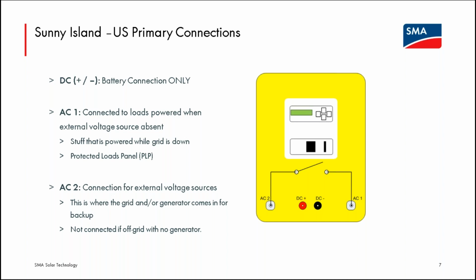If someone is using the system with a generator, the generator would also connect to the AC2 terminals. There is only one set of AC2 terminals in the Sunny Island. So if someone is using this device as a grid-tied backup device and they have a generator, there needs to be a transfer switch outside of the Sunny Island that will switch the AC input from the grid to the generator, because the output of that switch still would wire to AC2. There's only one set of AC terminals coming into the Sunny Island. If somebody was using the Sunny Island off-grid without a generator, nothing connects to AC2, but that's not very common.